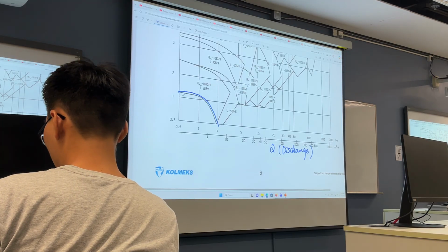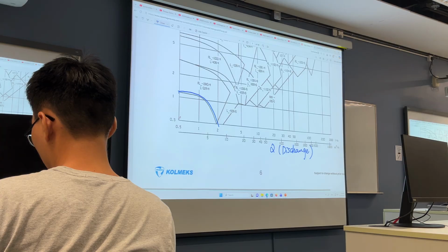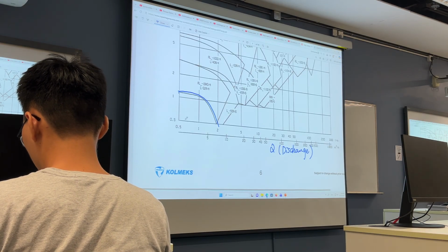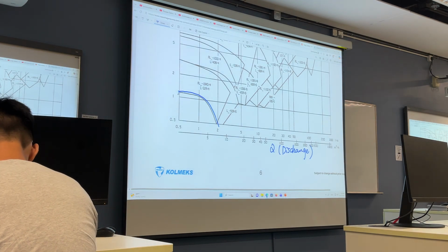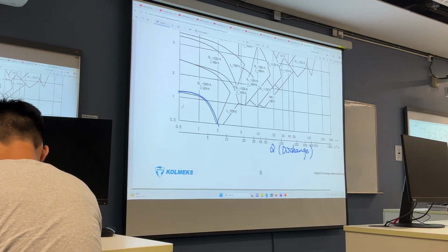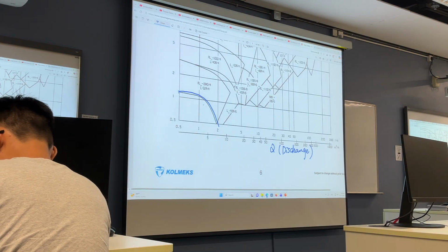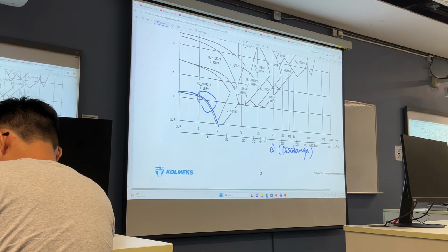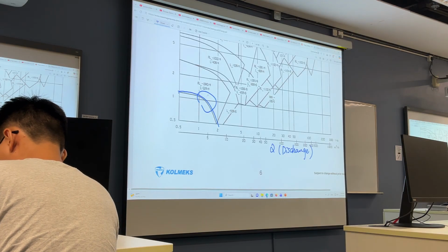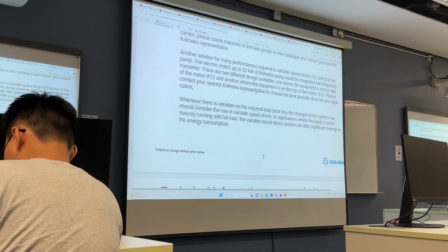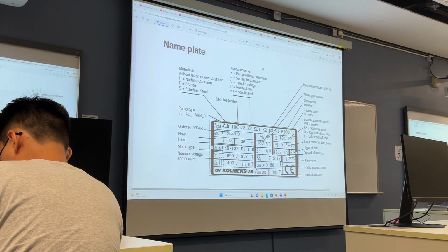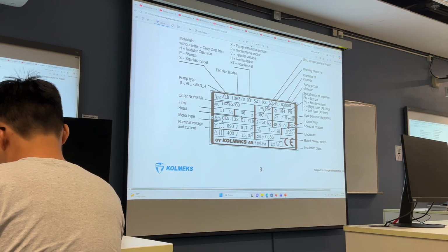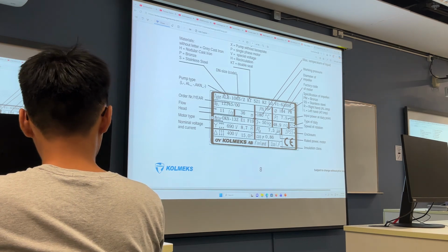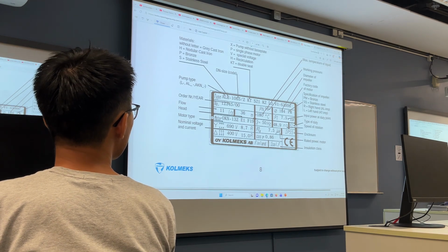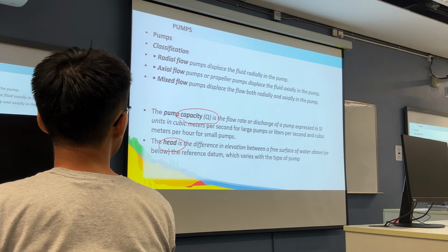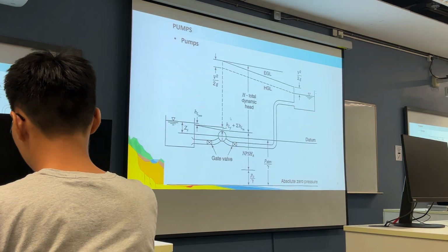If you want a higher discharge, the pump can usually provide only less pump head. If you want the pump to lift the water to a higher location, the discharge will not be that large. So the better range for using the pump is usually the middle range, to have higher efficiency. Some catalogs will also provide this. Now this is another type of pump plate. This one is 7.5 kilowatts, a relatively larger pump. Now, we mainly focus on the capacity and the head the pump can provide.